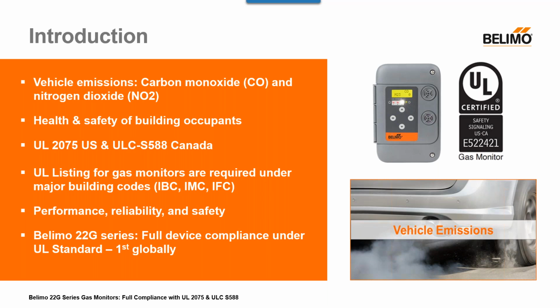The HVAC industry relies heavily on rigorous certification standards, importantly UL 2075 in the US and ULC S588 for Canada. These standards are among the most critical benchmarks for evaluating gas detection systems, and they stipulate stringent requirements for performance, reliability, and safety. While UL listing for gas monitors is required under major building codes, as mentioned, the IBC, International Mechanical Code, and the Fire Code, it is still not common for all manufacturers to obtain this UL 2075 certification.